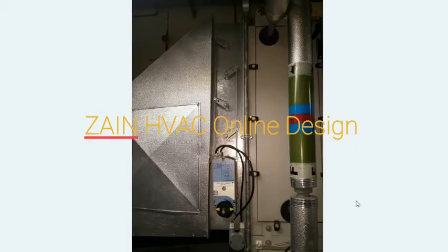And this is just a photo of one of the control units for the dampers on an AHU. And so this is being sent a controls signal to tell this to change its position, and that's a small motor inside which is going to turn this, and that causes these rods to rise and fall either way, and that will change the position of this rod here, and on the inside of the duct is the damper.